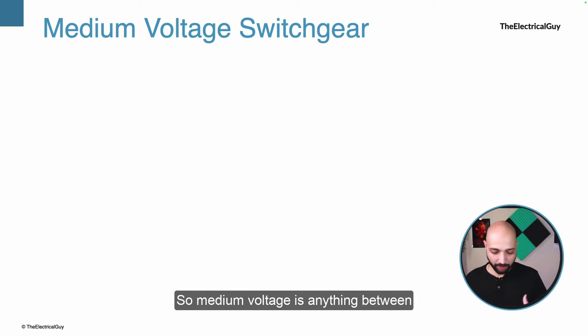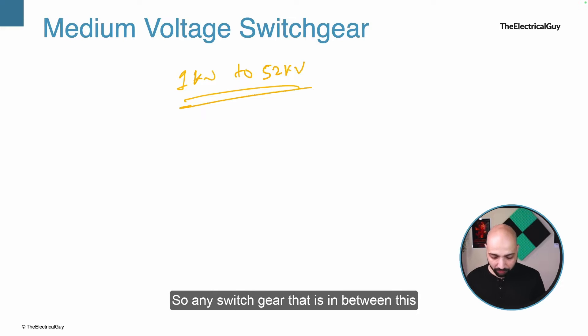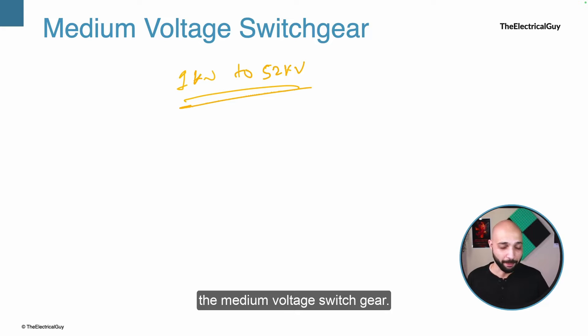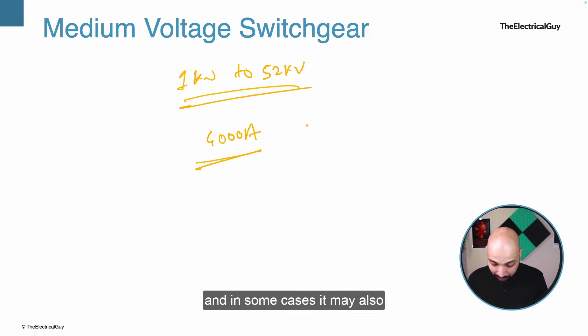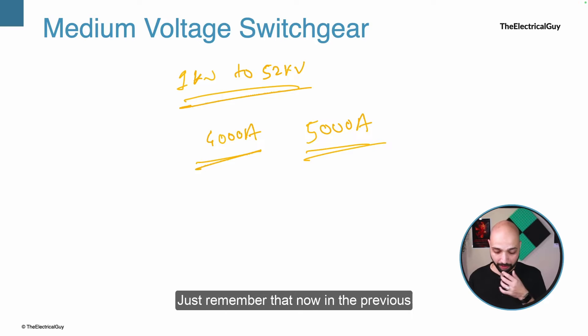Medium voltage is anything between 1 kV and 52 kV. Any switchgear in that range is considered medium voltage switchgear. The current rating can go up to 4000 A and in some cases may also go to 5000 A.